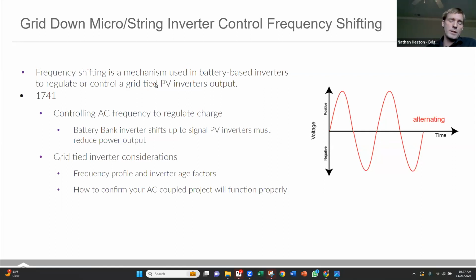The microinverter, or sorry, solar equipment, sorry, it was Victron equipment in that last slide, right? Mimics the grid. Well, what happens if there's nowhere for that power coming out of the Fronius to go, right? Those battery banks are charged, the loads are met. We need something to tell that string inverter to stop producing so much power, curtail the power, throttle it back. And the way that you do that is you need equipment that's capable of frequency shifting. So the Victron equipment there will shift the frequency output of its signal when the grid is down, right, to curtail the output power of either microinverters or string inverters in the case of the previous example.